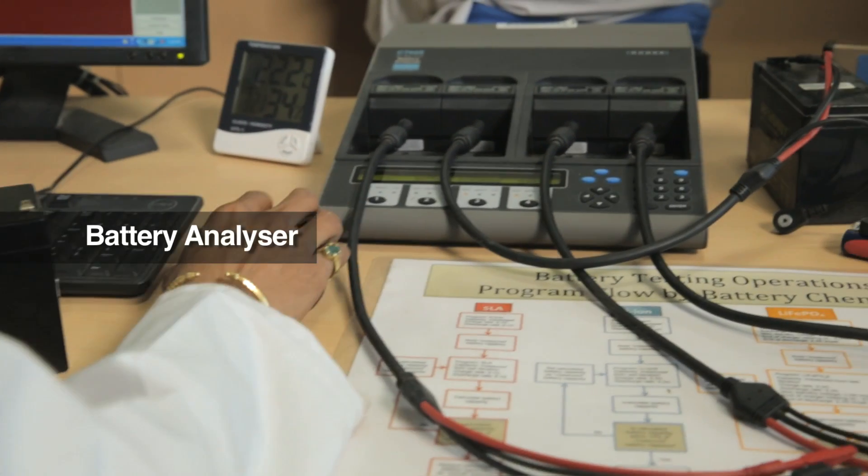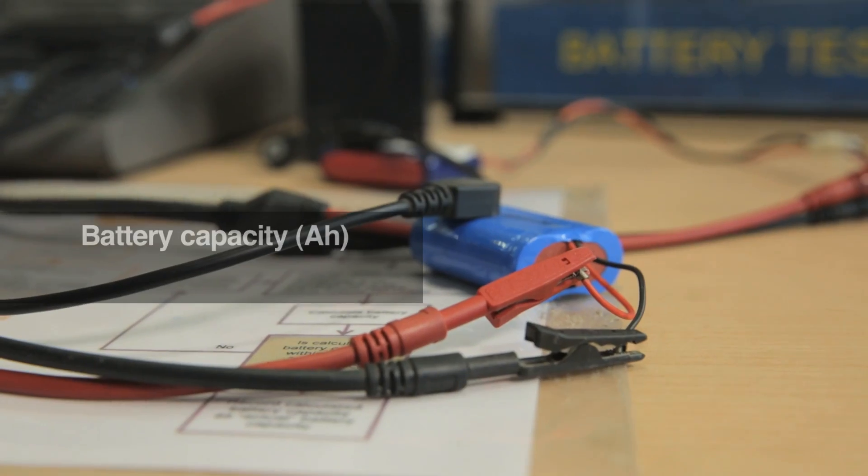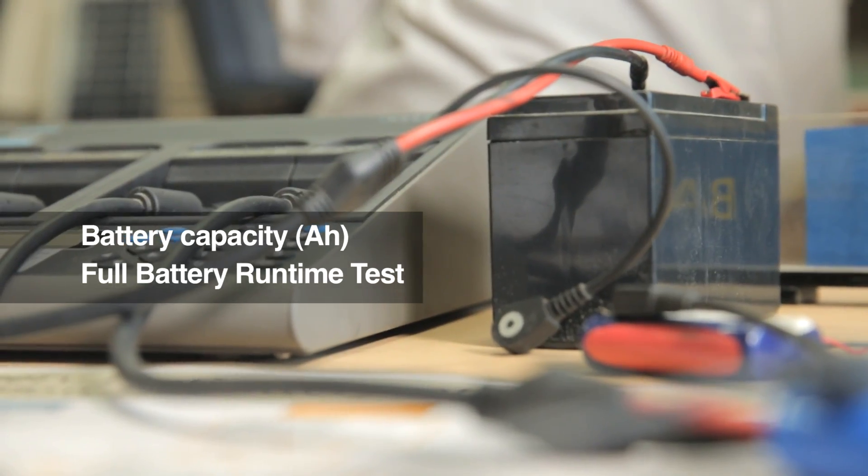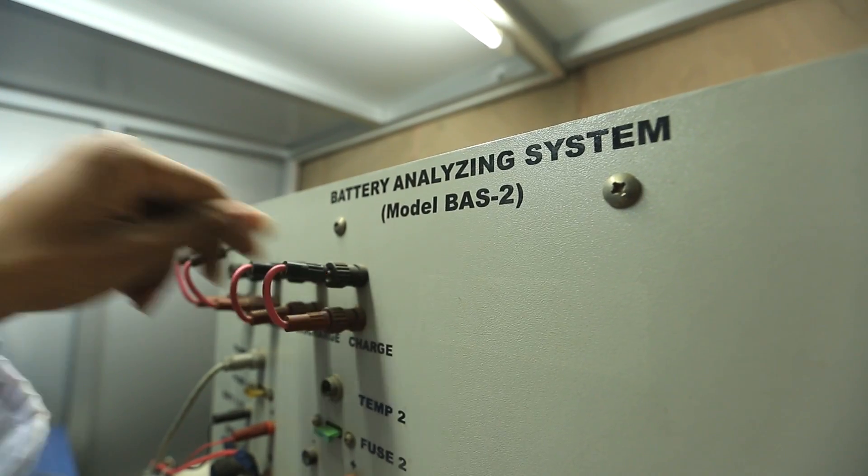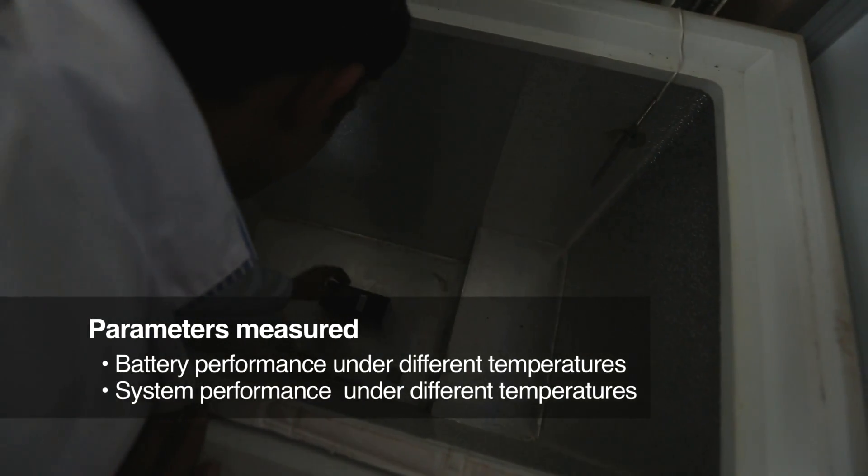The battery analyzer is to perform a variety of tests such as the battery capacity test, full battery runtime test, and performance of battery under different temperature conditions by using environmental chambers.